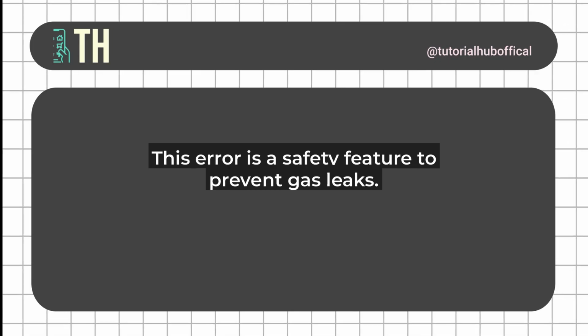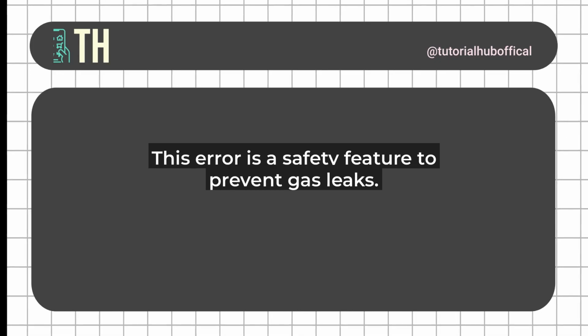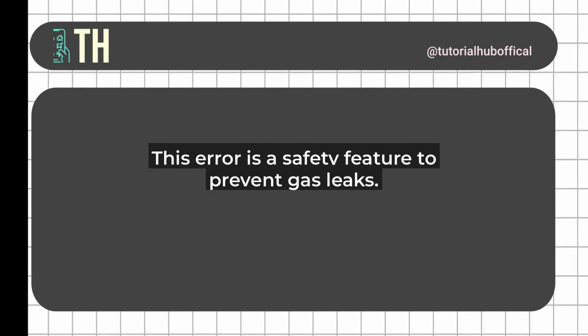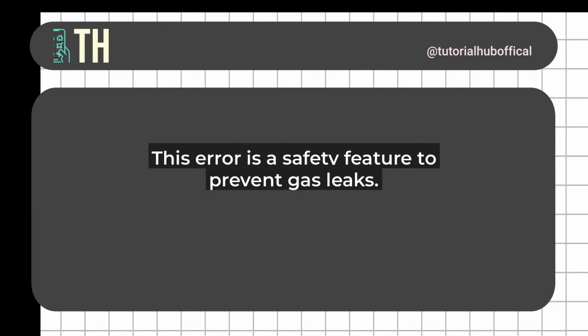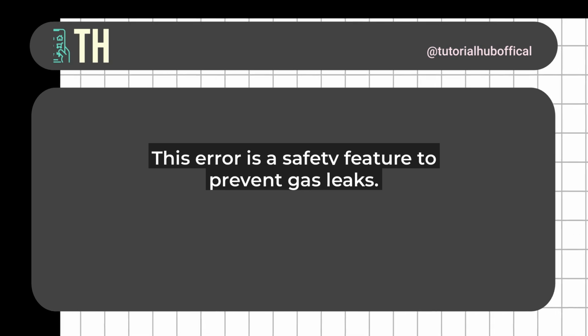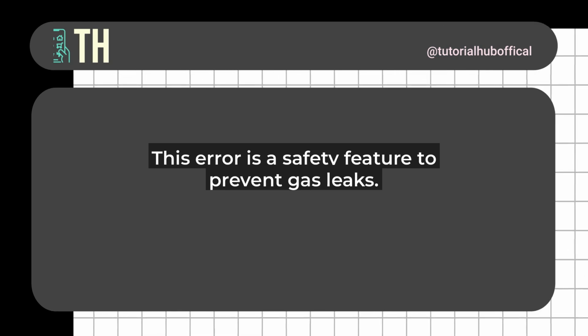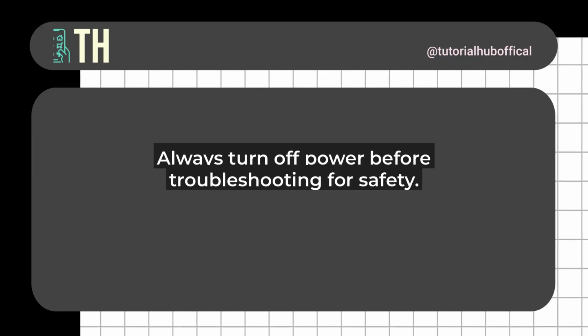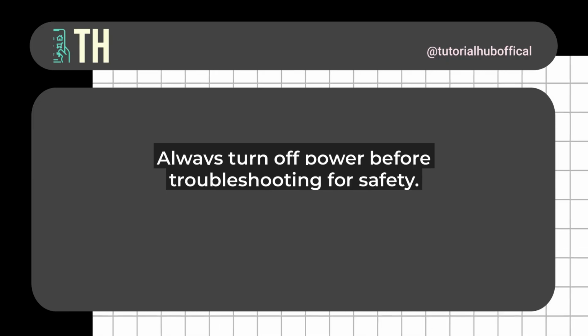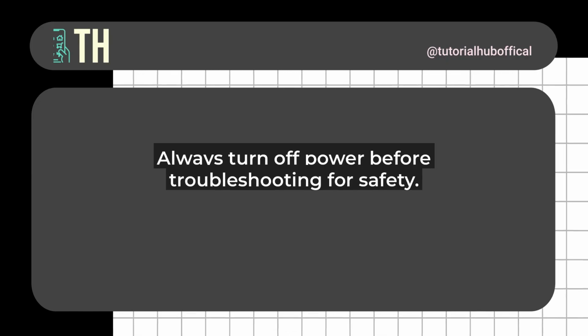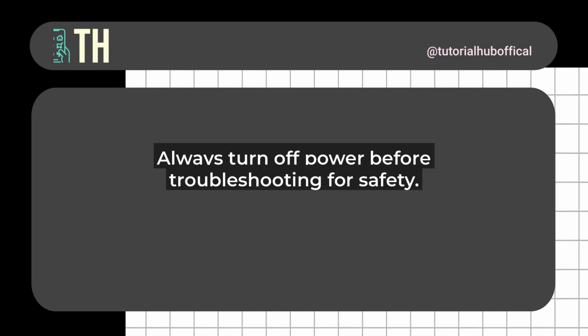First off, what does the 5 flashes mean? On a Honeywell water heater, this error typically signals a problem with the flame sensor or the gas control valve. It might indicate that the sensor isn't detecting a flame properly, which could be due to a faulty sensor, dirt buildup, or even issues with the gas supply. This is a safety feature to prevent gas leaks, so it's important not to ignore it.